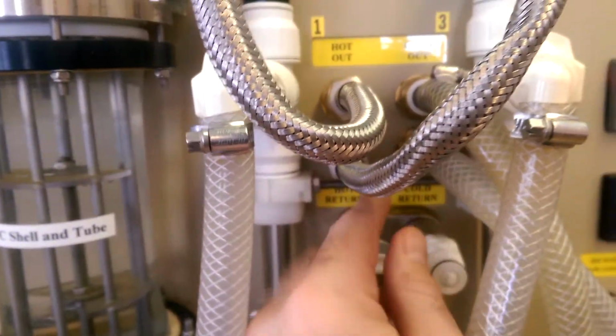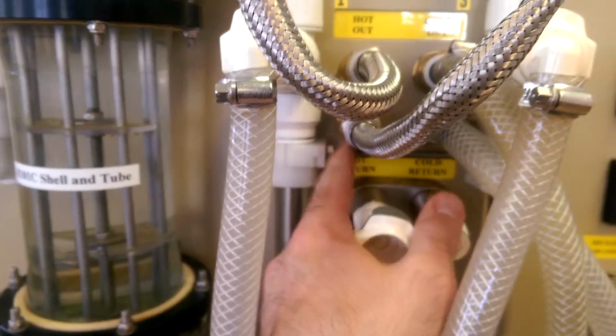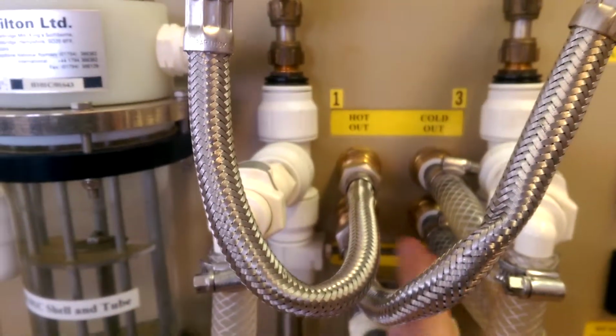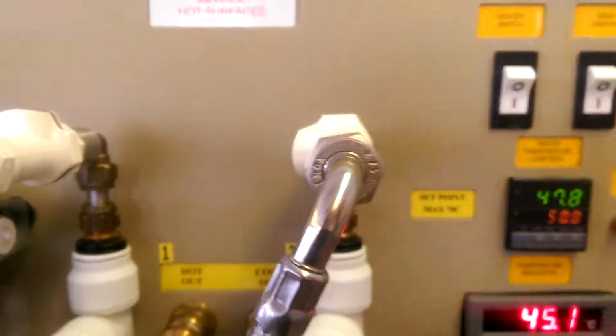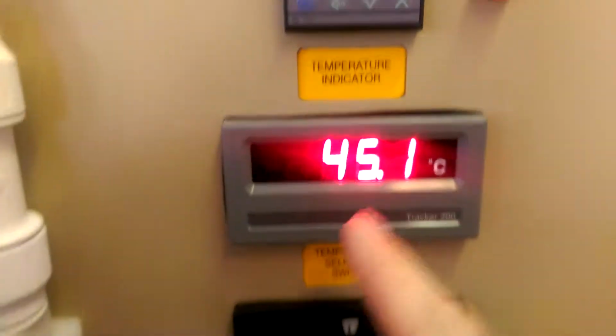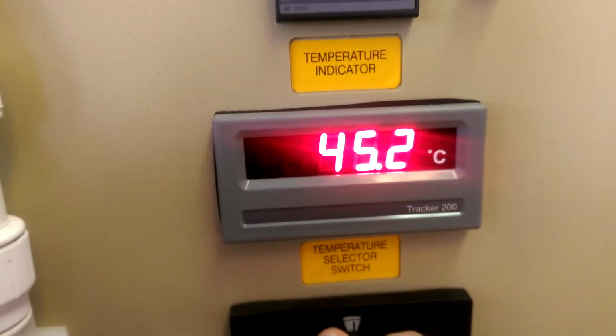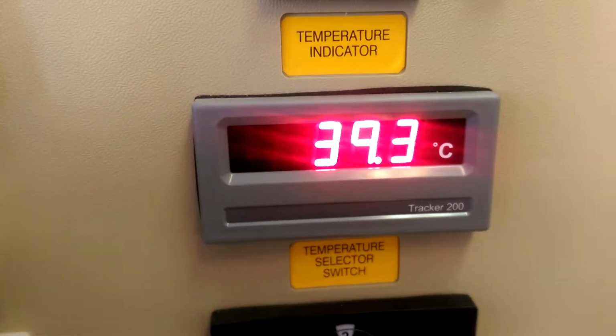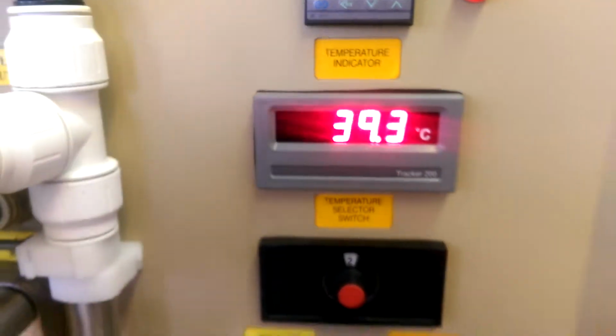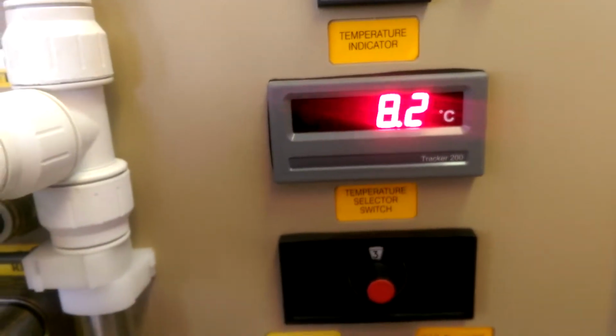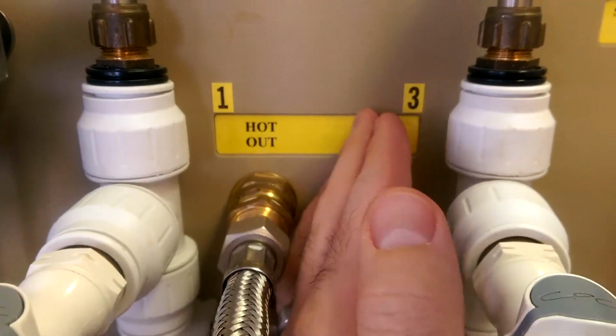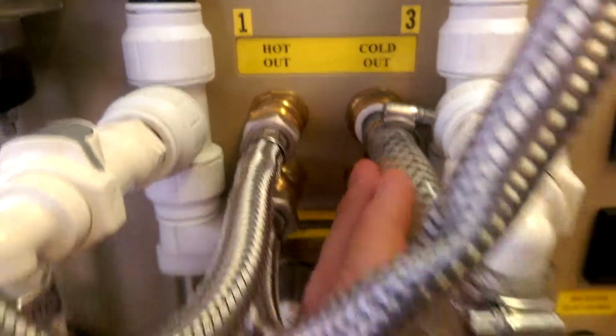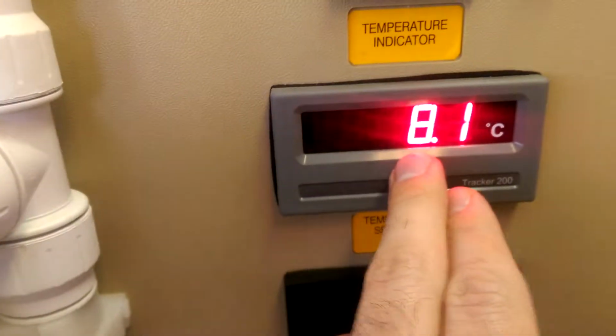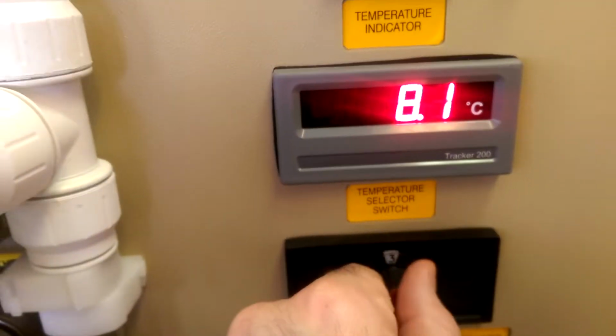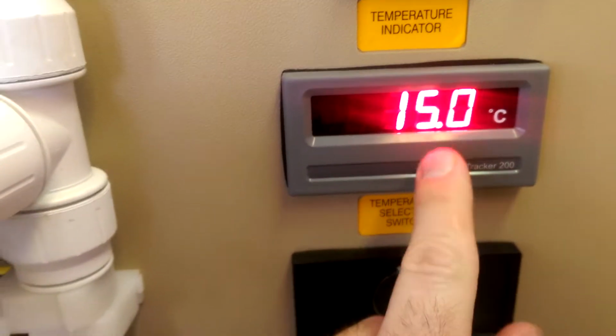T2, which there should be a number 2 here, you can't quite see it because I think it actually fell off, but T2 is basically coming back into the hot water unit, which is coming out of the heat exchanger. So T1 is hot water into the heat exchanger. If I switch it to T2, that's the hot water out of the heat exchanger. T3 represents cold out of the unit. So basically it's cold water coming out of this unit into the heat exchanger. So it's the temperature of the cold water into the heat exchanger, T3, and then T4 will be the temperature of the cold water coming out of the heat exchanger.